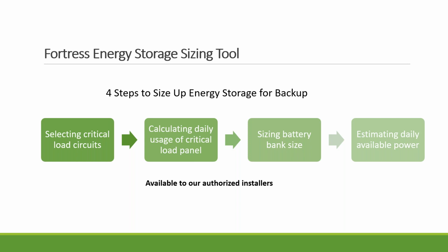And then based on the circuits that you selected, you can get a daily usage to determine how big a battery bank you want to have. At the end, you can also give your customer a breakdown of the average production and consumption of the house, to help them adjust their consumption behavior during the summer and the winter season. Because in some places, like here in the Northeast, the solar radiation ratio between summer and winter is 2 to 1. So in summer, you're going to produce double the amount of solar, which in winter is only half that. How you're going to power your house will be completely different.